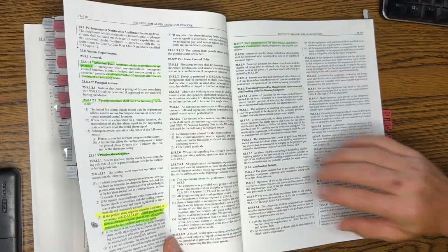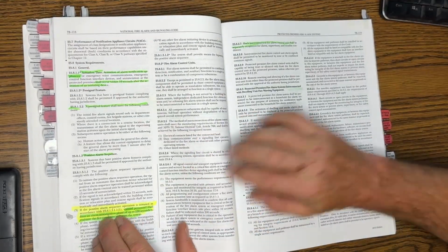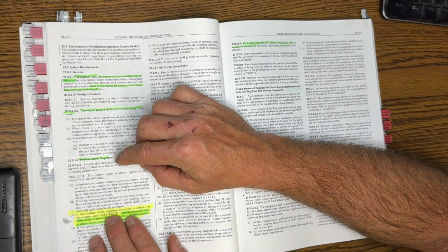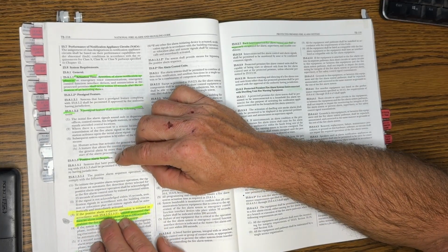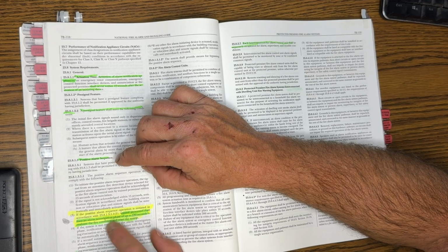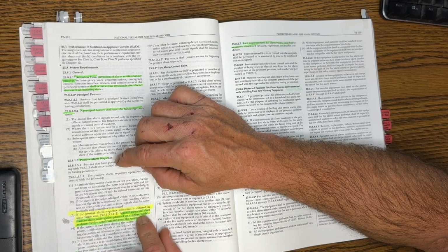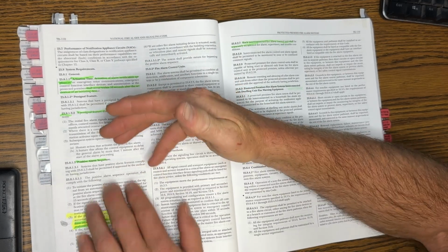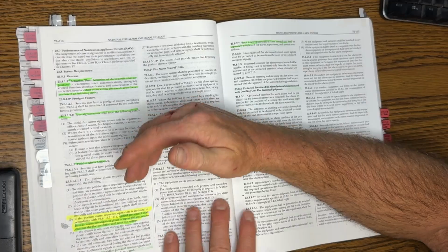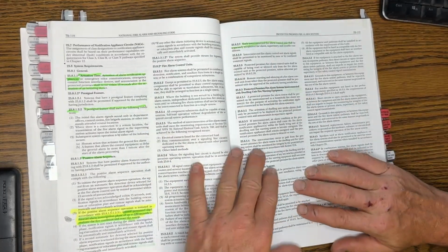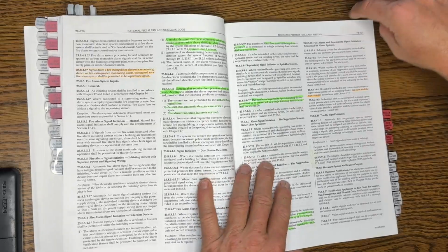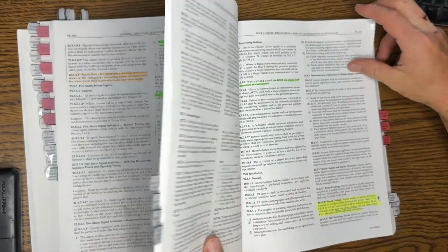All the stuff I've highlighted would be beneficial, but just specific emphasis on anywhere I have a pencil mark. If the positive alarm sequence operation is initiated in accordance with such and such section, trained personnel shall have an alarm investigation phase of about 180 seconds to evaluate the fire condition and reset the system. So basically a positive alarm sequence is a runner service type thing. You have some time to go out and look and make sure it's an alarm before you send a signal to the fire department. Let's see, I think I have one more here.